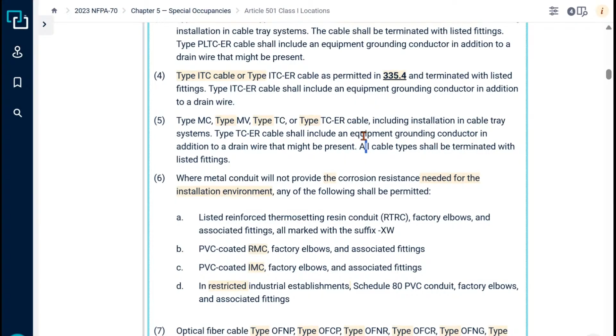But for the most part, just remember that ER means that at some point it can go from segment to segment, or it can leave the tray and go into a raceway or extend to a piece of equipment that is outside of the tray assembly, okay? That's all you've got to really remember for that. Let's see here. And of course, down here, it says where metal conduit will not provide the corrosion resistance needed for the installation environment, you have other allowances here: PVC coated RMC, PVC coated IMC, yada, yada, yada. You have optical fiber cables, a whole list of them here. Cable buses can be installed in those areas.